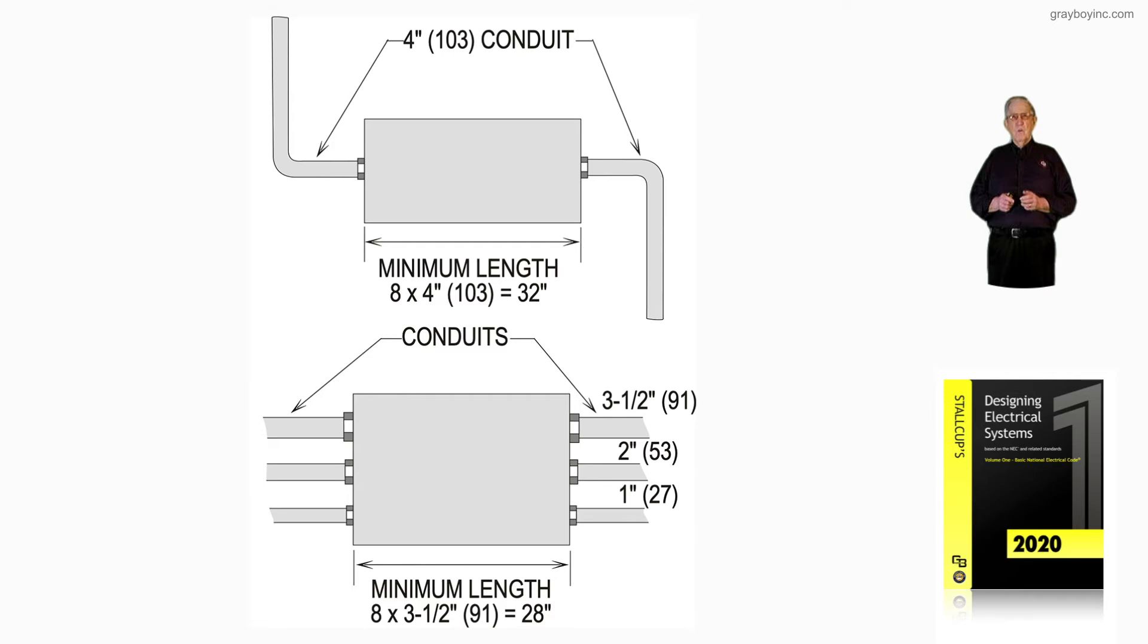Now the one at the bottom, you have more than just one conduit. So you would take the largest conduit, which is three-and-a-half times eight, and that would give you the length. So you can see it's eight times three-and-a-half, 28 inches.